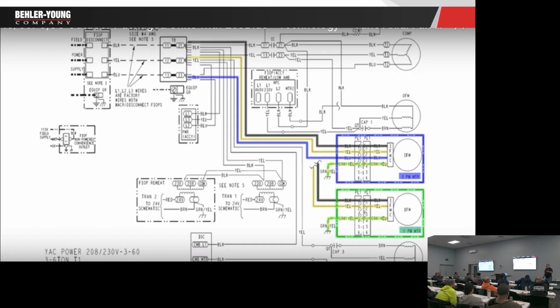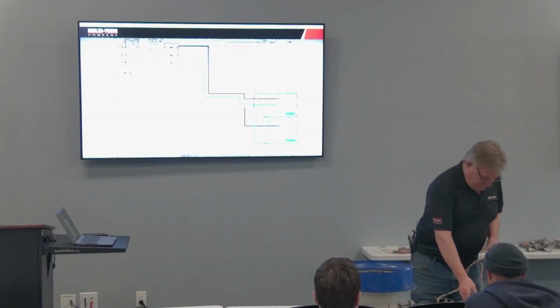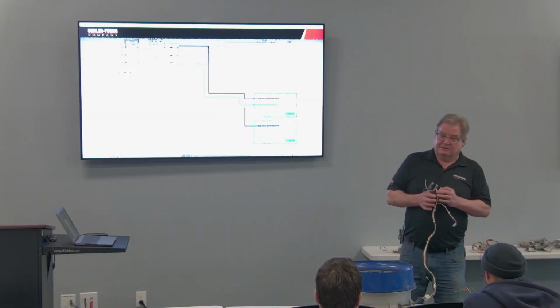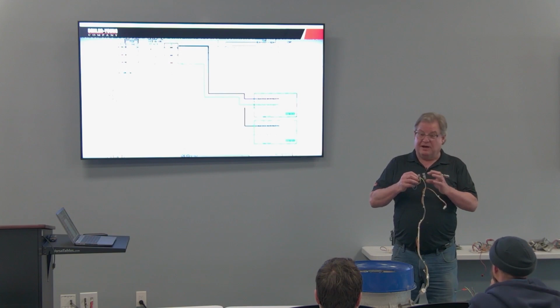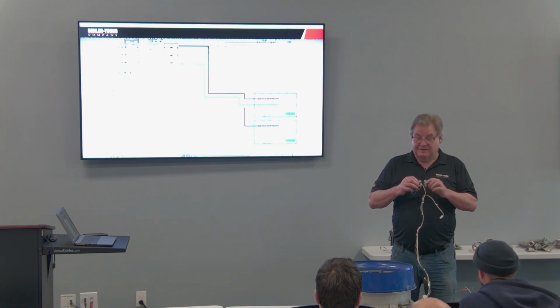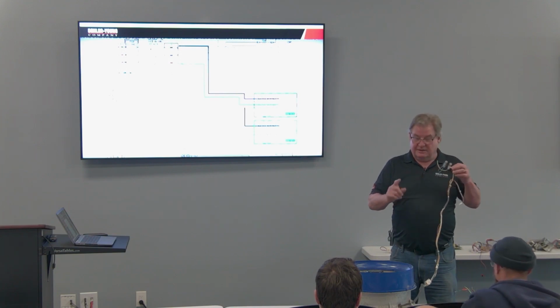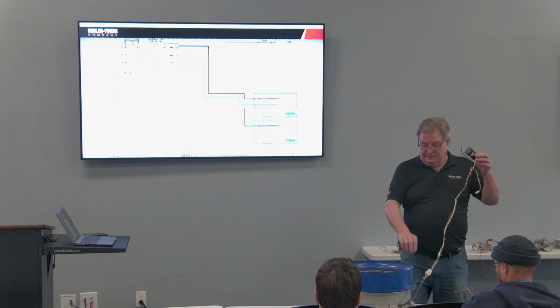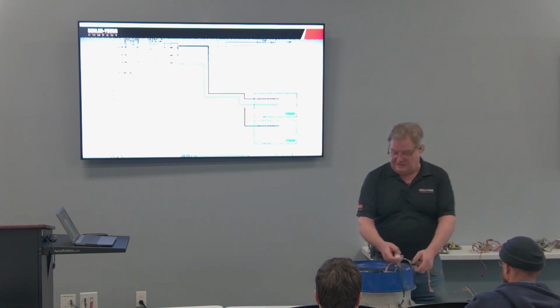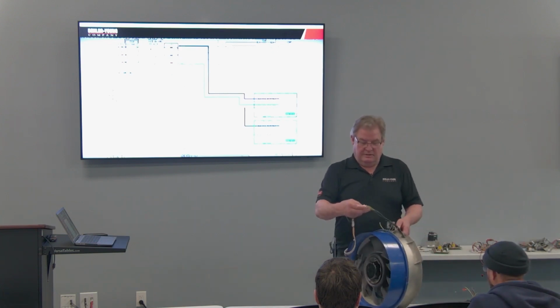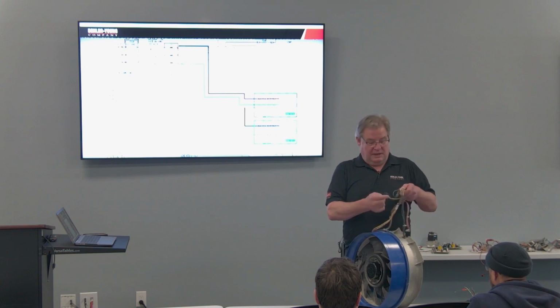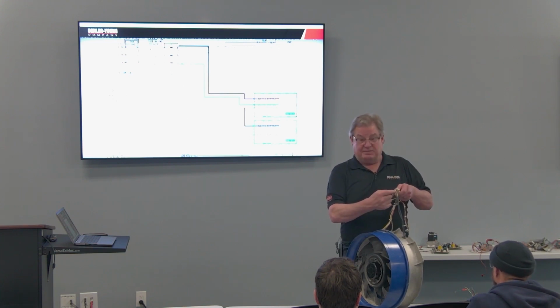All right, so obviously the first test of that motor is, does it have line voltage coming to it? Now, personal experience tells me, and I'll tell you in a little bit and you're going to laugh, why we don't check it here. If I check voltage here, it doesn't mean it's getting there. So inside the blower compartment is this plug here. I want to check it on the motor side of this plug.